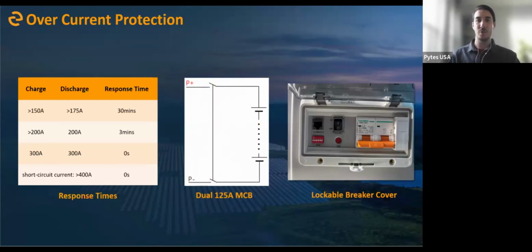If you did employ that ESS emergency stop that I showed before and the breaker trips, you do have to go out and manually reset the breaker, even if the emergency stop condition was reset. So it's kind of like a one-way street there, but typically something that's just employed in the case of emergencies. And that's another benefit of the MOSFET-based BMS as well.